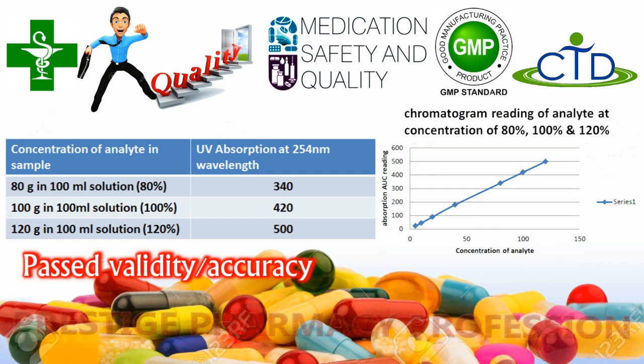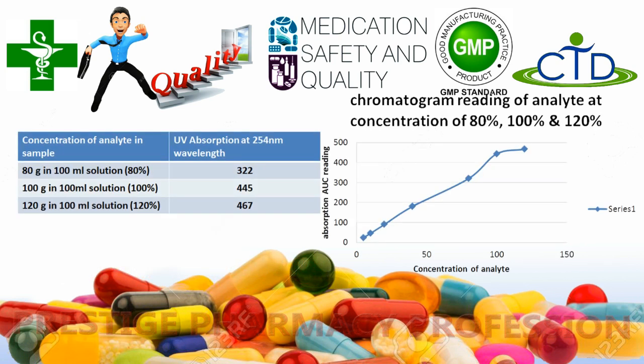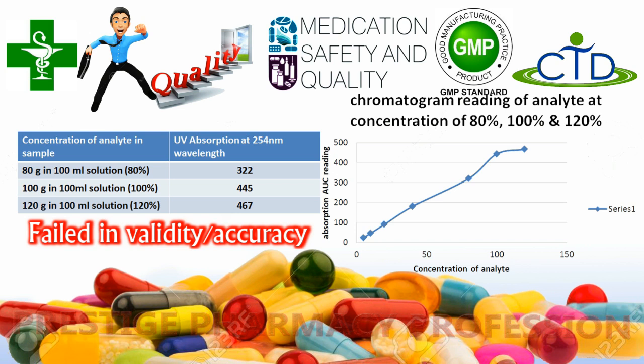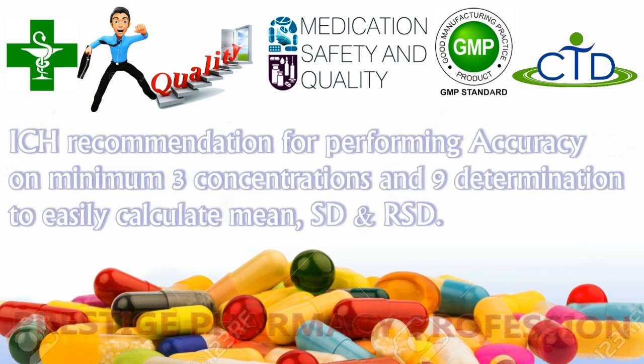For example, if an analyte sample of known concentration of 80 percent gives a UV absorption of 340, then increasing the sample concentration from 80 percent to 100 percent should increase the UV absorption to approximately 420 in a linear range, as shown in the diagram. If a linear graph is obtained with respect to concentration and UV absorption, the analytical method is acceptable and validated in terms of accuracy. If the analyte at different concentrations does not give a linear graph, the method is not correct and needs to be changed.